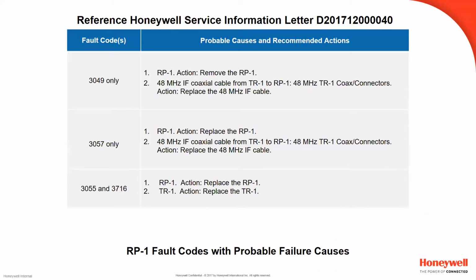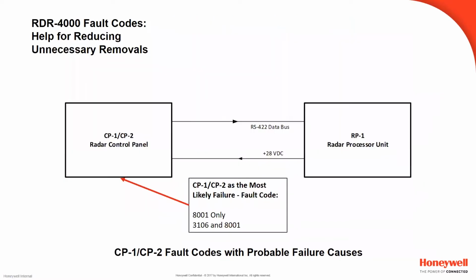A 3055 will get logged when the digital receive processor detects the formatted pulse data message inactivity fault. That is, when there is no pulse data message received for 2 seconds and the radar is in transmit mode, then this fault usually gets logged. And the 3716 would be logged when the RDSP visual ARINC 429 antenna status bus fails in monitor state. And this fault would also log a WXR INOP and a PWS INOP when the antenna status bus is inactive. So for all of these fault codes, the first troubleshooting step would be to replace the RP, and then would follow the next troubleshooting. Now we're moving to the control panel faults.